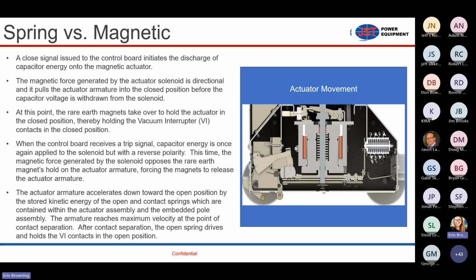So in order to change the position, for example, to force that armature downward, a signal of a certain polarity is sent to the actuator from the capacitors. That allows the magnets to release their hold and allows the armature to move downward. This centerpiece right here is a spring and acts like an open assist. So if we need to trip the breaker, that spring decompresses rapidly and allows that armature to get pushed downward because the magnets are no longer holding it up. And then once it's down, it stays down and it stays open until it receives a close command from the controller, at which point the magnetic field that builds up in the inductor pulls the armature upward and then the magnets hold it up. And if that sounds like a mouthful, it's because it probably is.